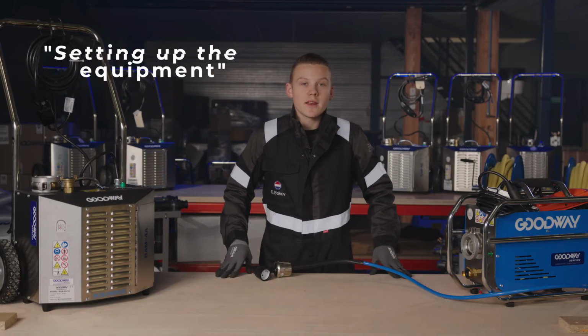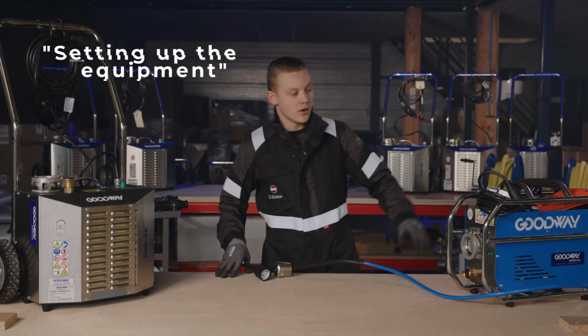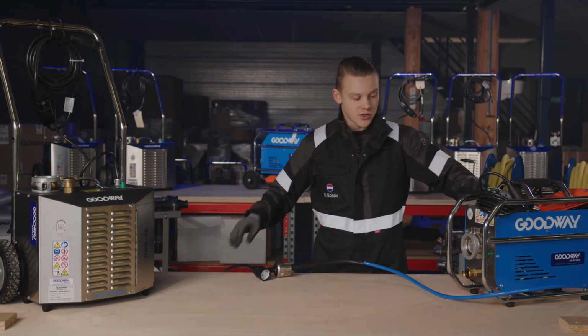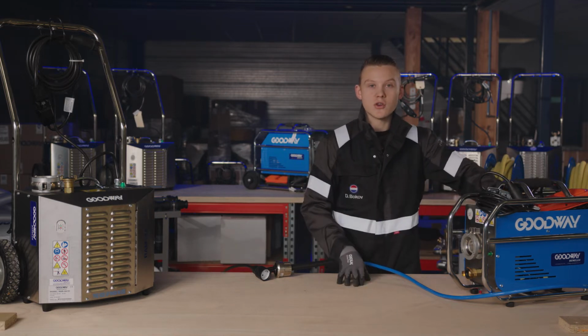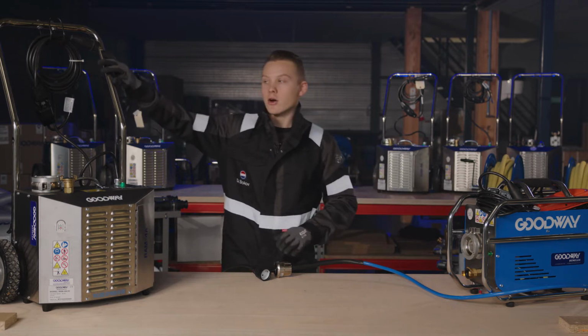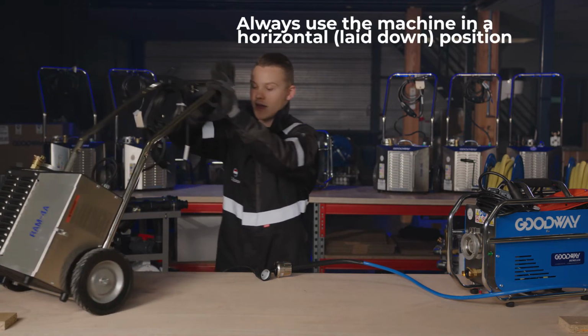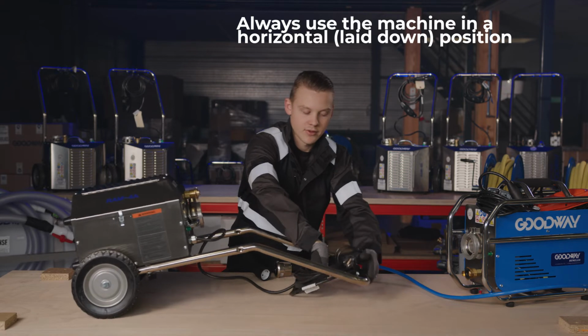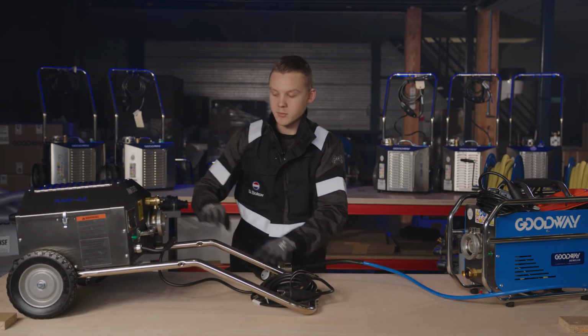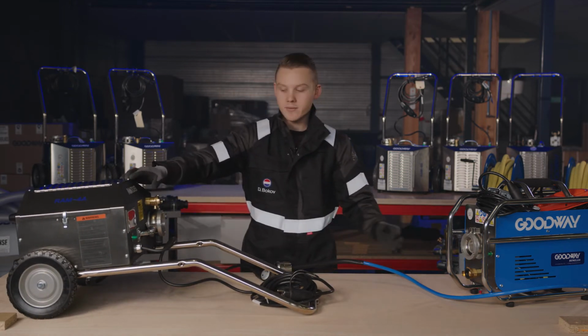Setting up your tube cleaning system is very easy. When you're using a system with a roll cage, you can put it like this and go on straight away. When you have a dolly though, it is important to lay the system down when you're going to use it. Why is it so important? Because it's important that the shaft goes out in a straight way. When you have it going out with a bend, it can cause internal friction, which can cause the shaft to break earlier or have a shortened lifetime.